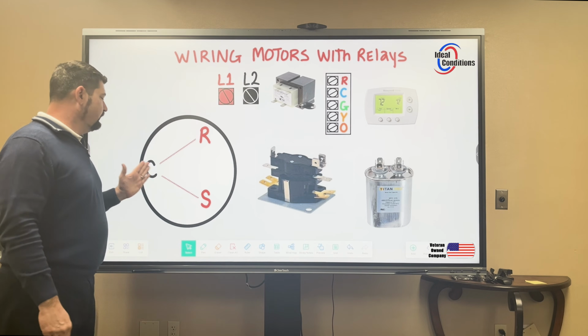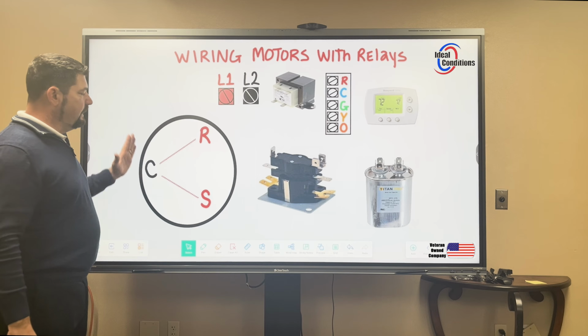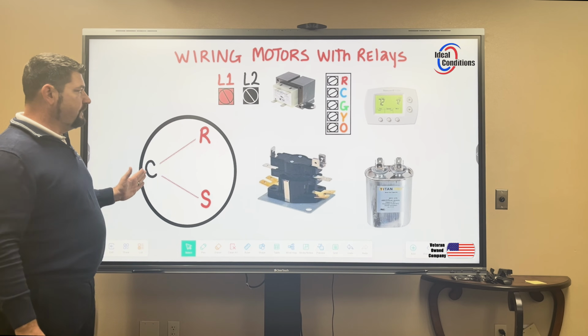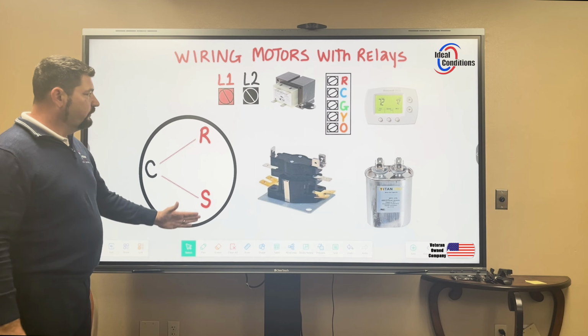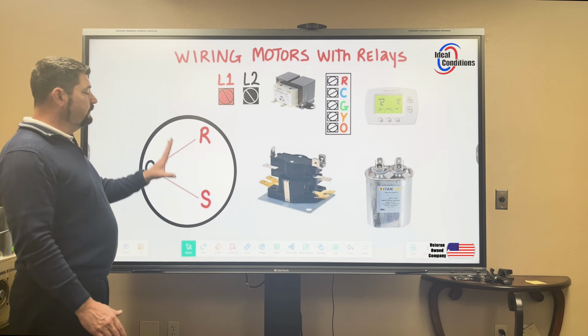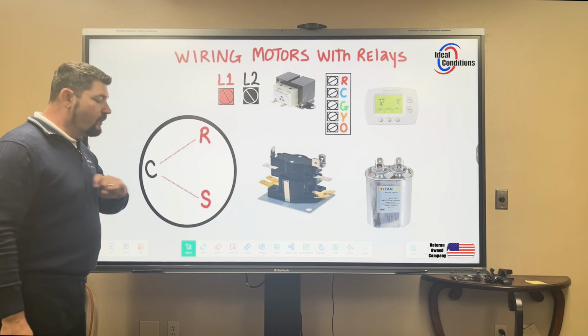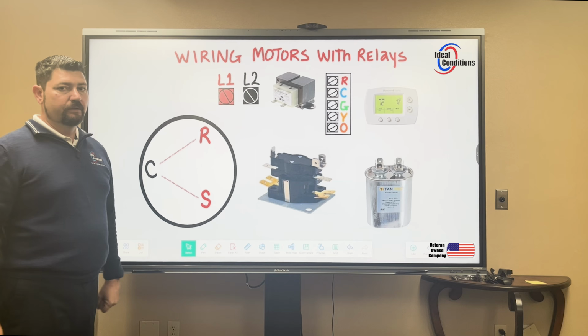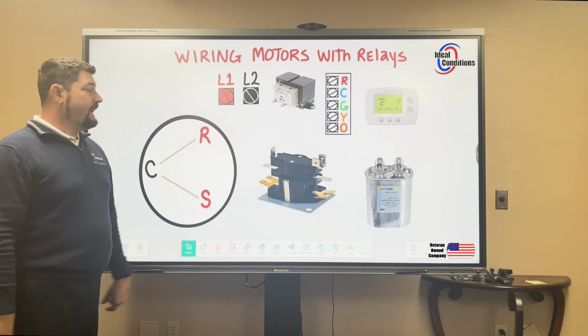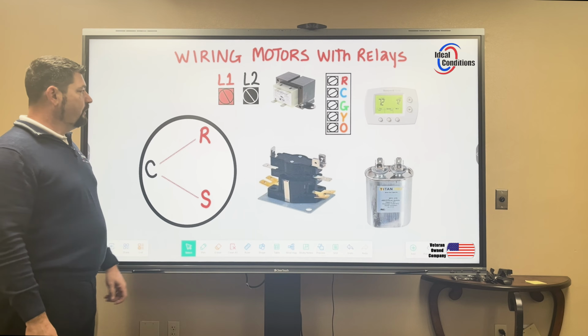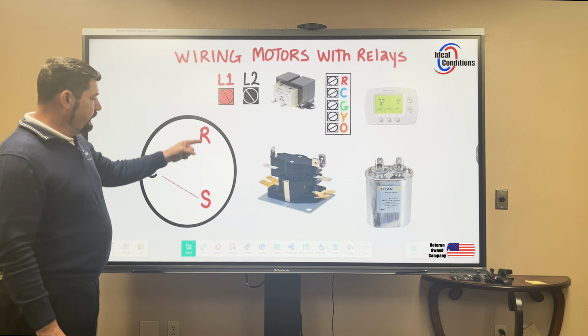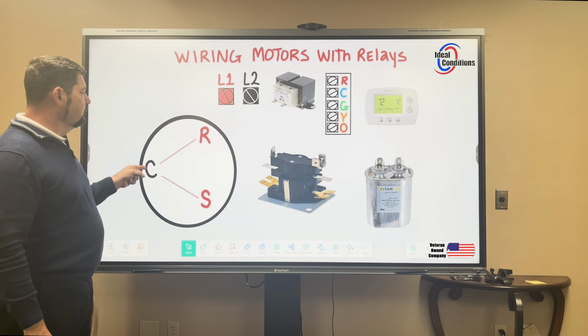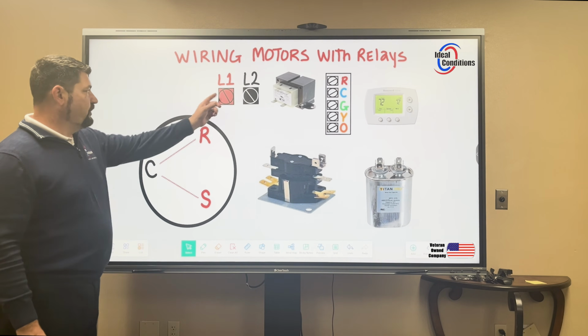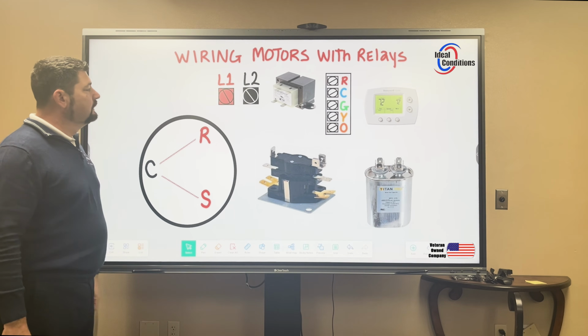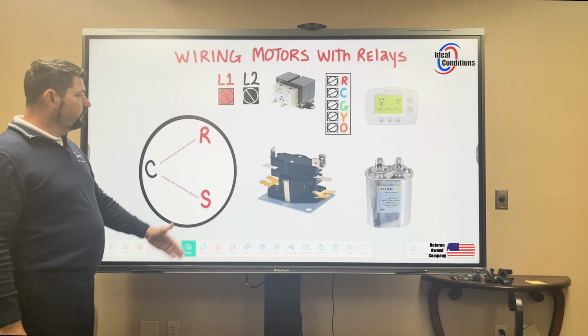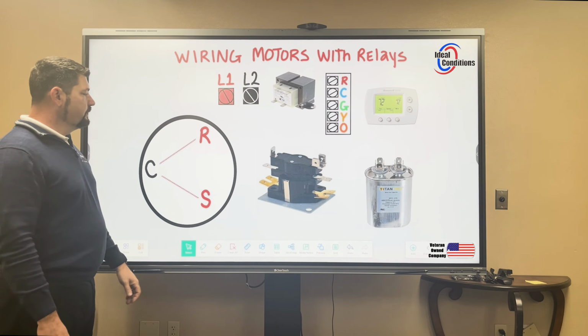If you look at my motor windings, I've labeled red and black. I wanted to distinguish — not that common has to be L2, not that run and start have to be L1. What I wanted to distinguish is that run and start are always on the same leg of power. That's what we need to get out of that. So if I wanted to rewrite this, these would have to be black, that would have to be red — I don't have to change anything here, but if I wanted to, sure, why not. As long as run and start are on the same leg of power, you're good.